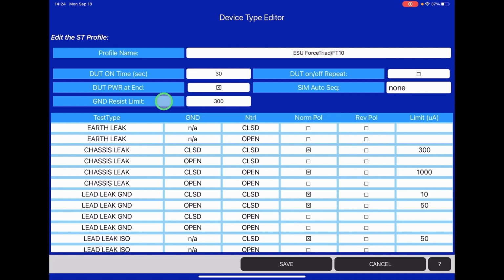The next limit is ground resistance test, or what they refer to as ground bonding test. We've set the limit per the manufacturer's requirements at 300 milliohms as well. Below this are the tests that we have to run per the FT10 service manual. And you have here the names of the different tests we could be running, from earth leakage, chassis leakage, to lead leakage to ground, or what's called leakage sink, leakage source current, I should say. And then you have lead leakage ISO, lead leakage sink. It can be referred to in the service manuals.